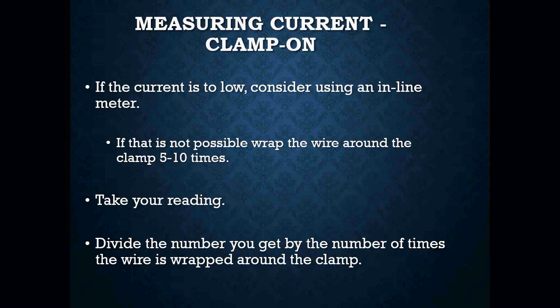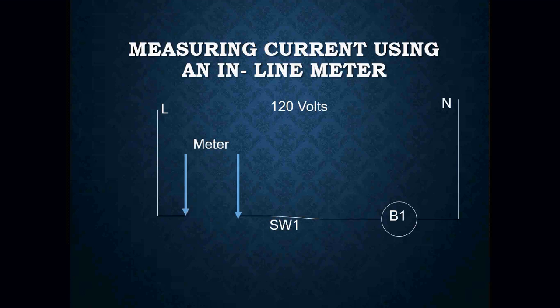Okay, if the current is too low, you may want to consider using an inline amp reading. Okay, if this is not possible, a way to get around that is take the wire and wrap it around the clamp about 5 or maybe 10 times if you can do so, and then take a reading. Okay, how to take that reading is you're going to divide the number you get by the number of times you wrap the wire around the clamp.